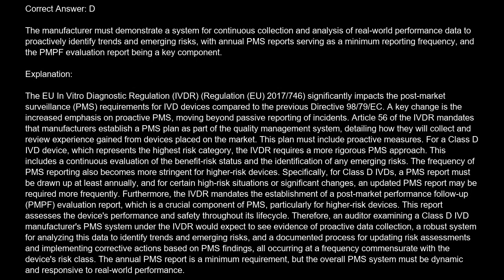The manufacturer must demonstrate a system for continuous collection and analysis of real-world performance data to proactively identify trends and emerging risks, with annual PMS reports serving as a minimum reporting frequency, and the PMPF evaluation report being a key component. Explanation: the EU In Vitro Diagnostic Regulation, IVDR, Regulation (EU) 2017/746, significantly impacts the post-market surveillance (PMS) requirements for IVD devices compared to the previous Directive 98/79/EC.